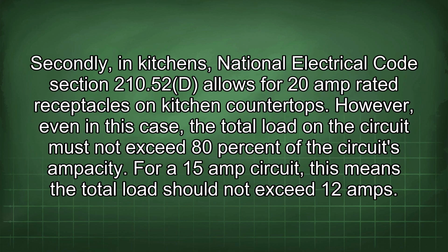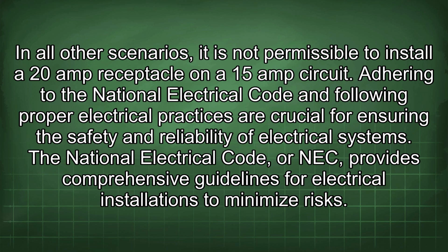Secondly, in kitchens, National Electrical Code Section 210.52(D) allows for 20 amp rated receptacles on kitchen countertops. However, even in this case, the total load on the circuit must not exceed 80% of the circuit's ampacity. For a 15 amp circuit, this means the total load should not exceed 12 amps. In all other scenarios, it is not permissible to install a 20 amp receptacle on a 15 amp circuit.